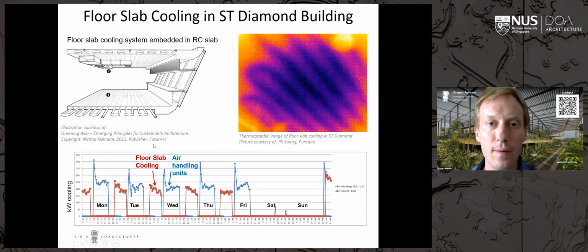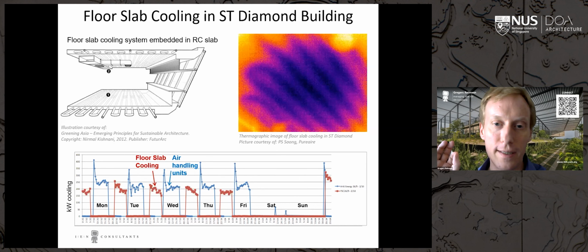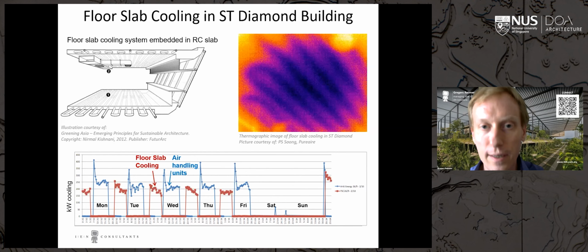And floor slab cooling, because you don't need to chill the water all the way to 6 degrees, which a normal chiller does. But in this case, you only need to cool it to about 18 degrees. So that means your chiller can actually run twice as efficiently because the temperature lift is smaller. Therefore, you can save a lot of money on this slab cooling because you benefit from a more efficient chiller, and you can consume the energy at night where the energy rate is cheaper.